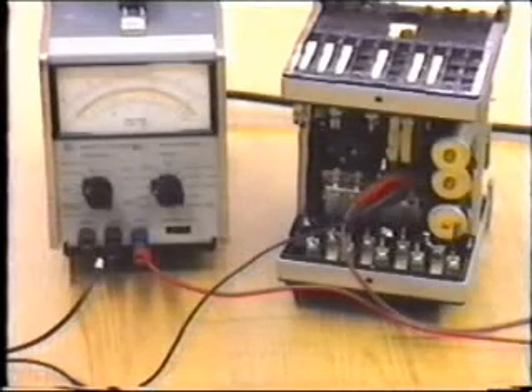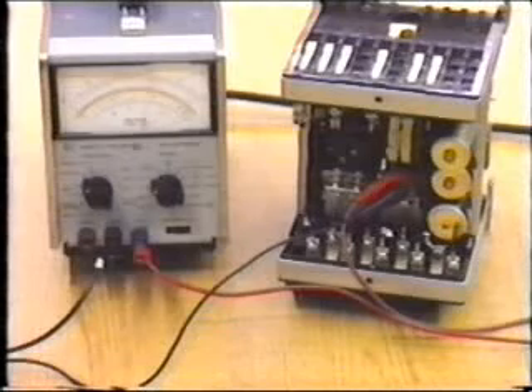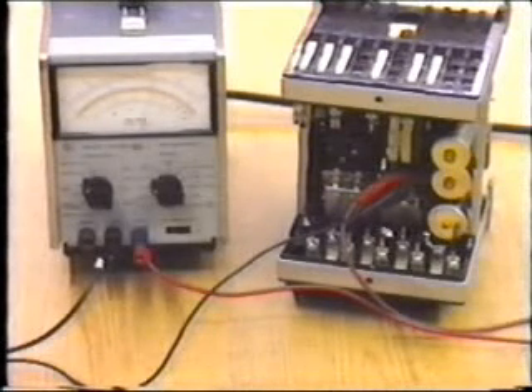Most ohm meters have a resolution of about 1/10 of 1 ohm, which somewhat limits their application for measuring very small resistance values. For example, in measuring the contact resistance of switchgear, special equipment must be used. We will use a low resistance tester which provides a relatively high current at a very low voltage.